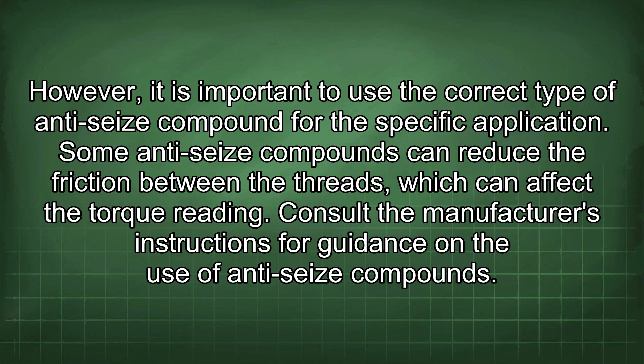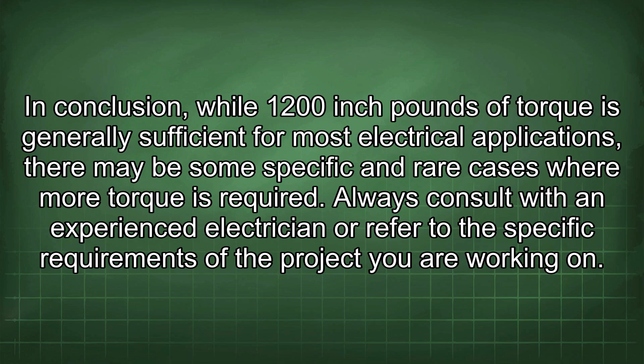In conclusion, while 1200 inch-pounds of torque is generally sufficient for most electrical applications, there may be some specific and rare cases where more torque is required. Always consult with an experienced electrician or refer to the specific requirements of the project you are working on. Follow safe work practices and use a calibrated torque wrench to ensure that electrical connections are properly torqued.